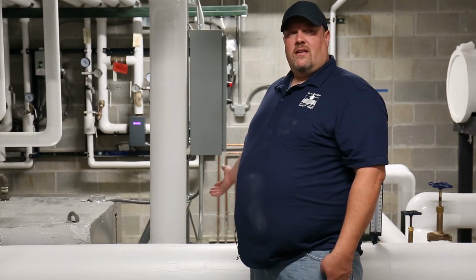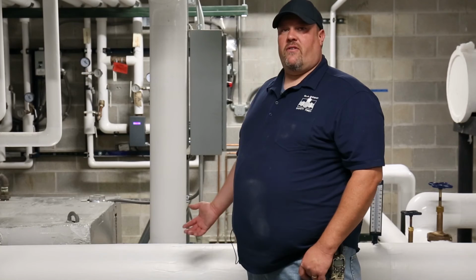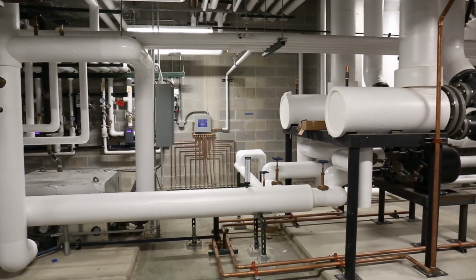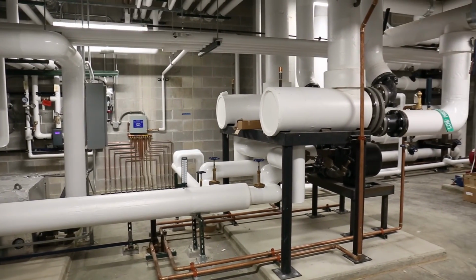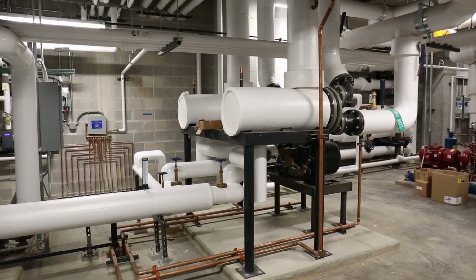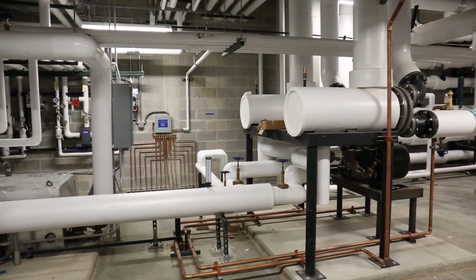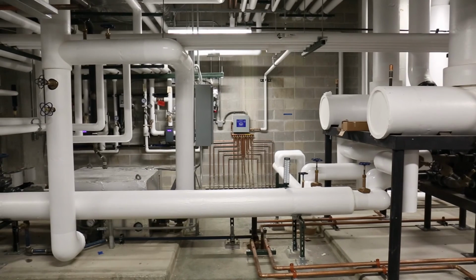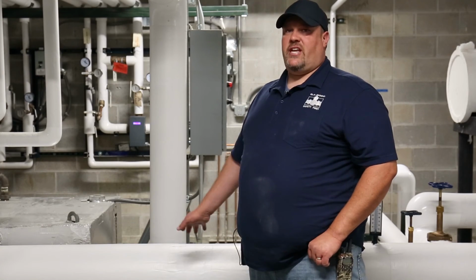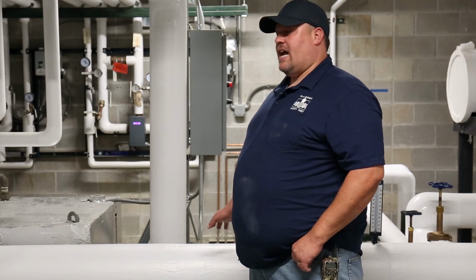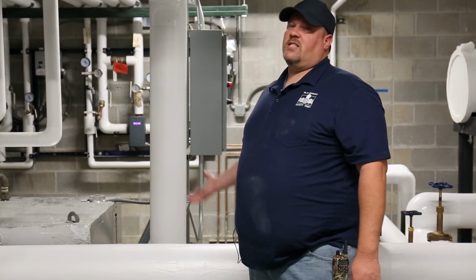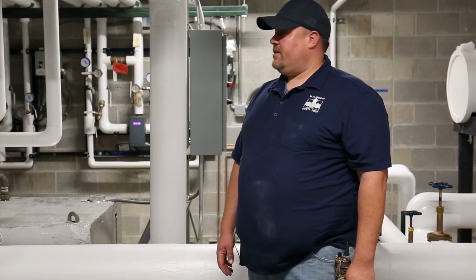Here we have our main condensate receiver for the building. At the current moment, we have the low pressure steam and the medium pressure steam both tying into this. Eventually, we will add in a medium pressure flash tank before it enters the condensate receiver, before it gets pumped back out to campus utilities.